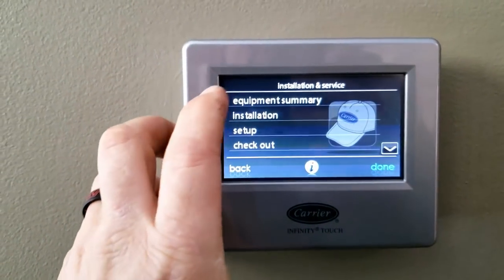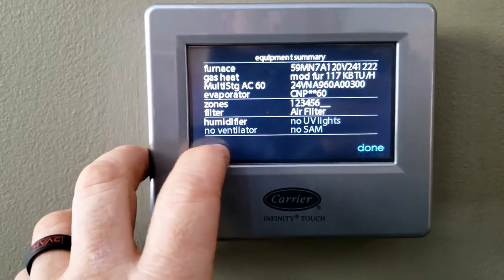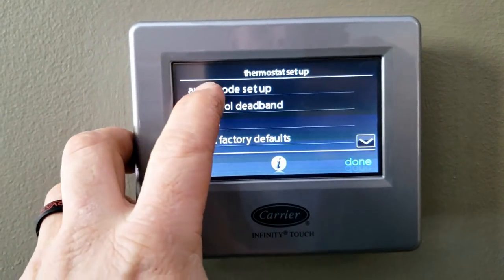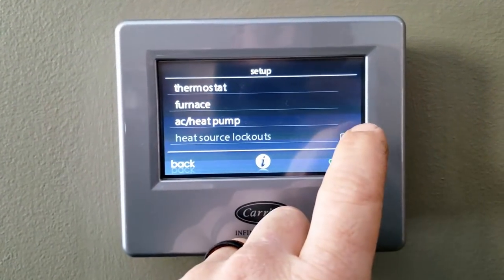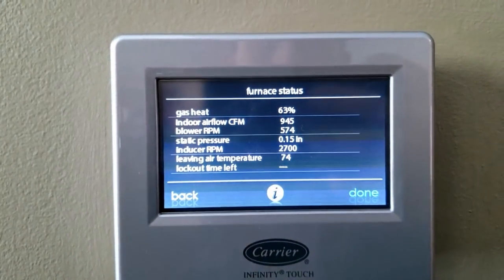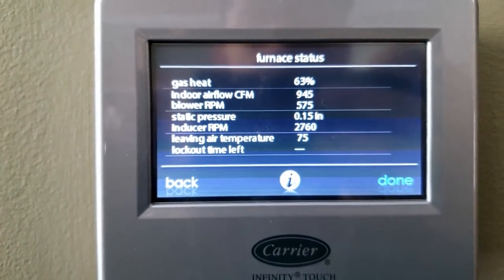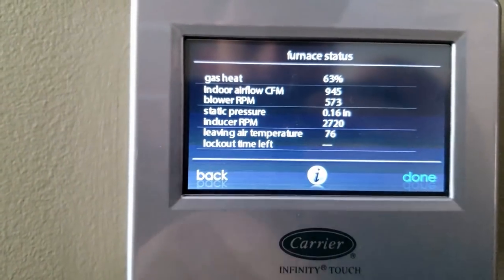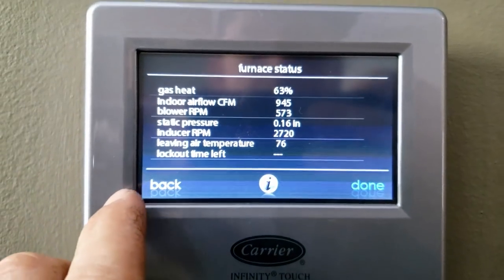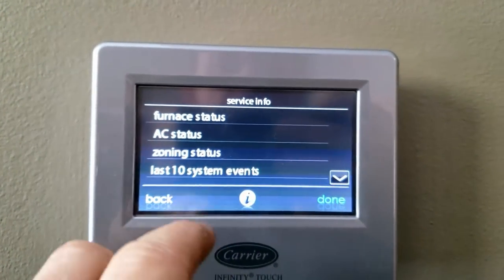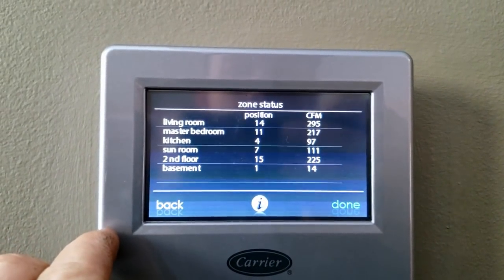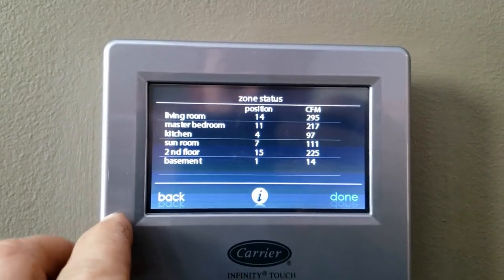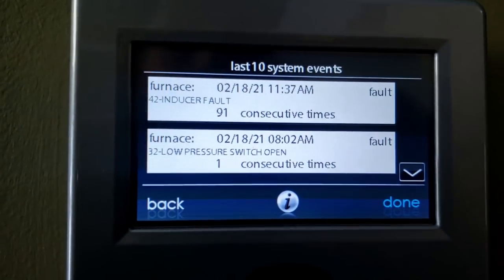Alright, this is what I like about Carrier compared to some of the other brands out there. You can see exactly what we've got here. We've got to set up a thermostat. We can see what all this happy stuff is. We can also go in here and just see what exactly it's doing. So on the service information, furnace status, you can see exactly what it's running at percentage-wise - the CFM, blower RPM, static pressure, draft motor, leaving air temperature. That's because of the zone panel. All that happy jazz. I know some of the other manufacturers got something close to it, but they've had this crap for a long time. So let's go into zoning status. And there's a few zones - three, four, five, six of them. And last ten events - my favorite part.